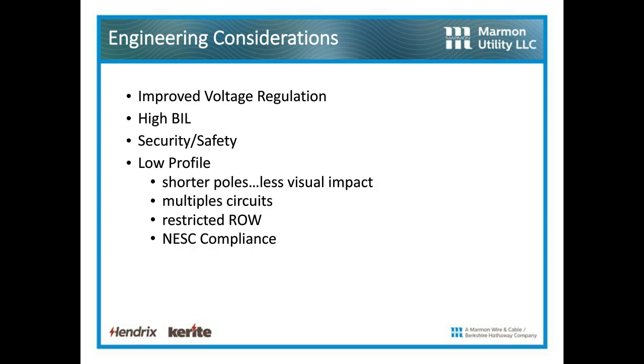If we go into engineering considerations, there are a couple that jump right out at you. The first is improved voltage regulation. We're going to have 15 to 20% better voltage regulation when we compare this to a bare wire system. We're going to have a very high BIL. We talked about security and safety. No energized conductor is ever safe, but this will give you a shock. It's not fatal, so it's safer, a million times safer than bare wire lines. It's going to be low profile, which means I can use shorter poles, with less visual impact. I can build multiple circuits, restricted right-of-way construction, and NESC compliance.